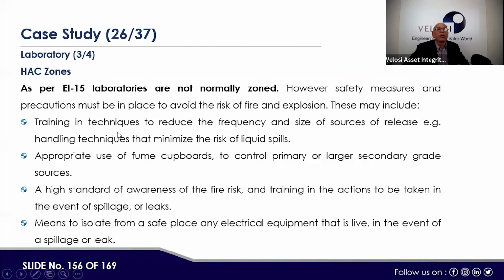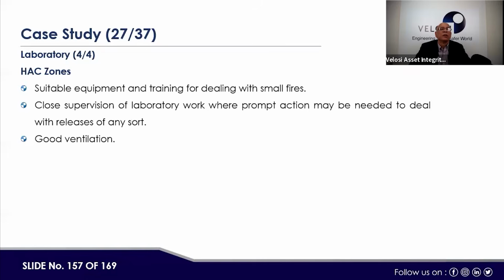These may include training of technicians to reduce the frequency and size of sources of release, for example handling techniques that minimize the risk of liquid spill, appropriate use of fume cupboards to control primary or large secondary grade sources, a high standard of awareness of the fire risk, and training in the actions to be taken in the event of spillage or leakage. Also means to isolate from a safe place any electrical equipment that is live in the event of a spillage or leak, suitable equipment and training for dealing with small fires, and close supervision of laboratory work where prompt action may be needed to deal with a release of any sort. Good ventilation is also required in the laboratories.